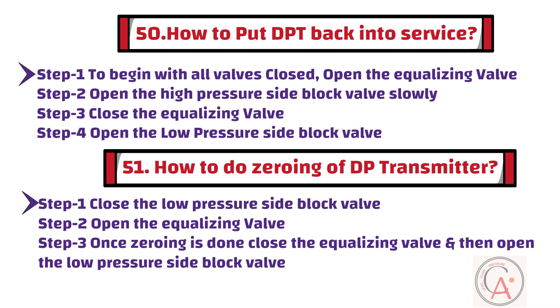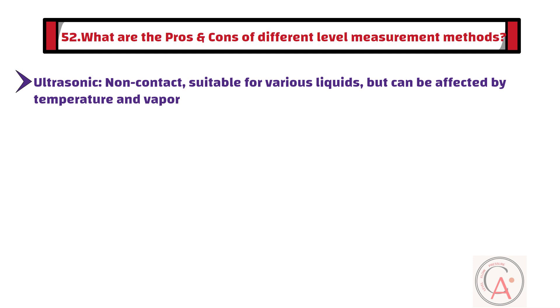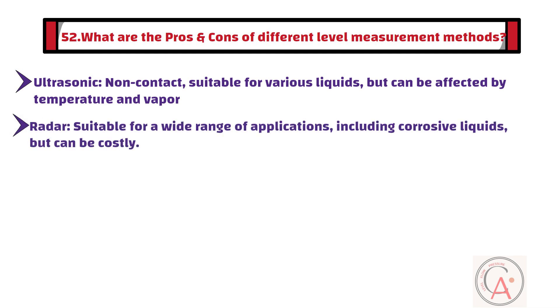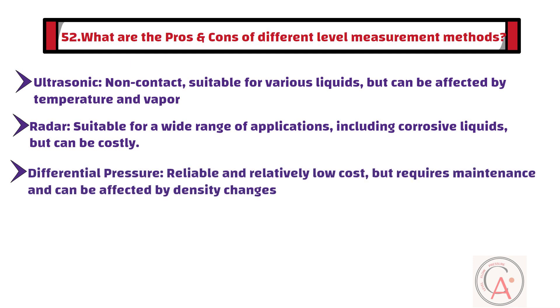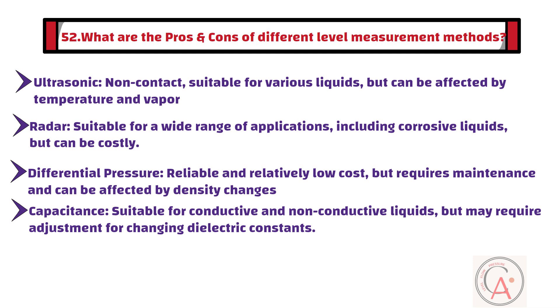Question 52: What are the advantages and disadvantages of different level measurement methods? Each level measurement method has its own set of advantages and disadvantages. For example, ultrasonic is non-contact and suitable for various liquids, but can be affected by temperature and vapor. Radar is suitable for a wide range of applications including corrosive liquids, but can be costly. Differential pressure is reliable and relatively low cost, but requires maintenance and can be affected by density changes. Capacitance is suitable for conductive and non-conductive liquids, but may require adjustment. The choice of level measurement method depends on the specific application's requirements and conditions.